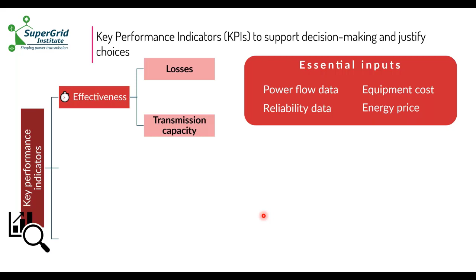The key performance indicators we use to compare these architectures are mainly effectiveness indicators — the total losses of the overall system and the transmission capacity of each interconnector — and reliability indicators, which are the expected energy not transmitted, related to curtailment: the energy lost because of the reliability of every component in the system.